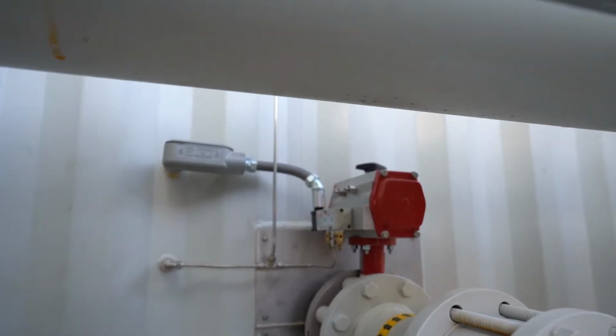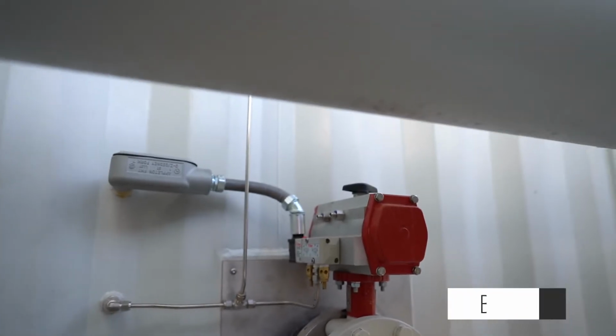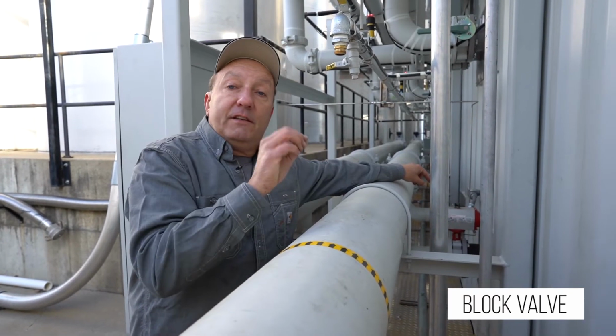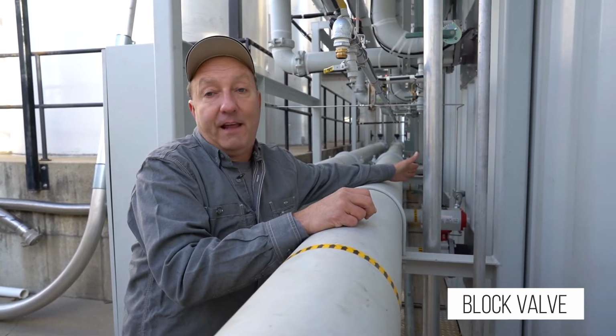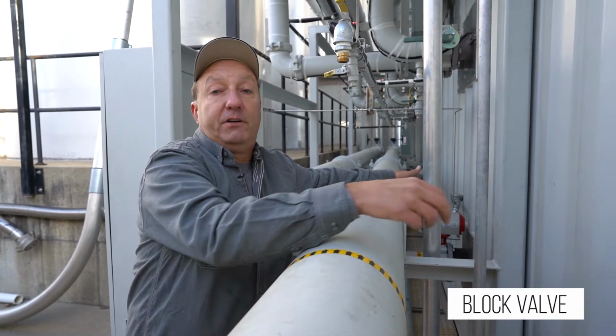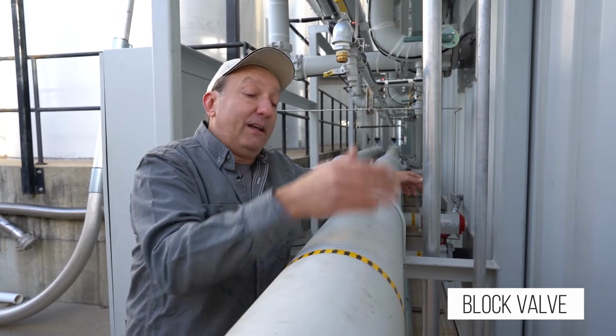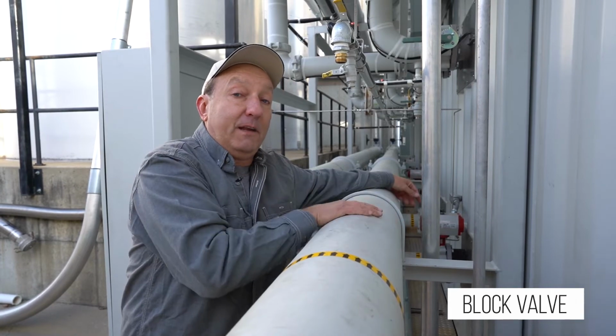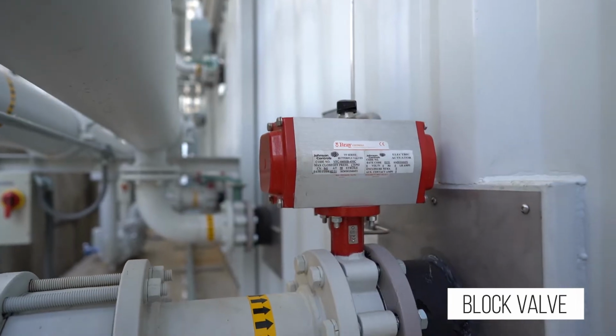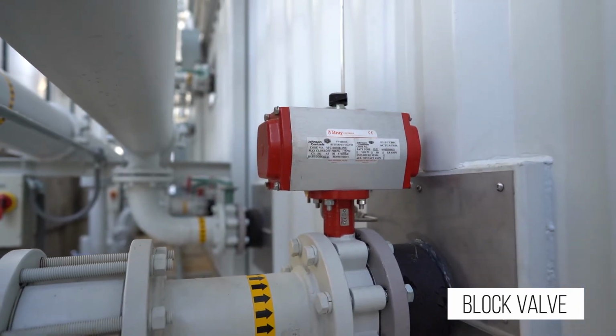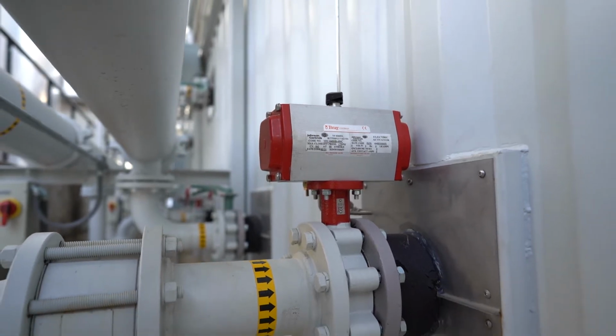And when we enable circuit 1, 2, or 3, we have a block valve. So when we initiate the start sequence, the block valve opens to that particular evaporator and we circulate through that evaporator. We can run all 3 circuits at the same time, but the block valve has to be enabled and it's all in a 1-button start and stop sequence.